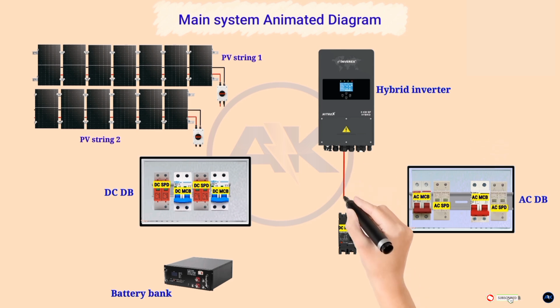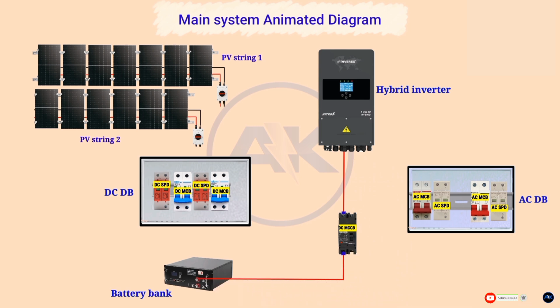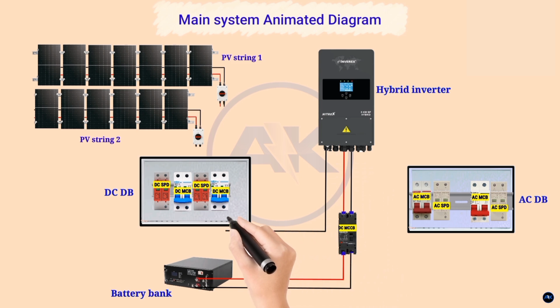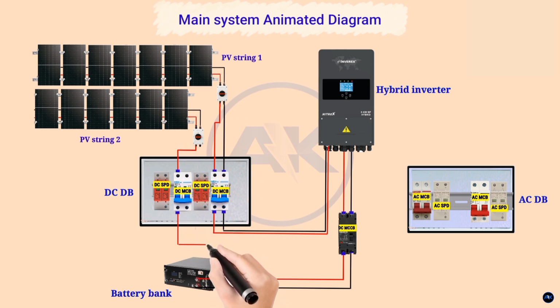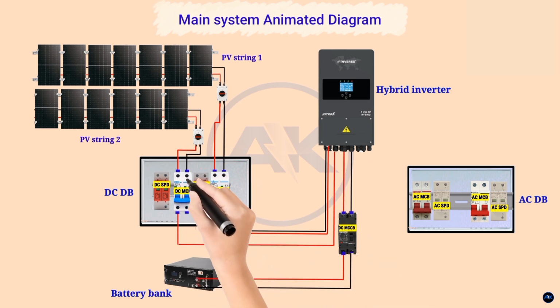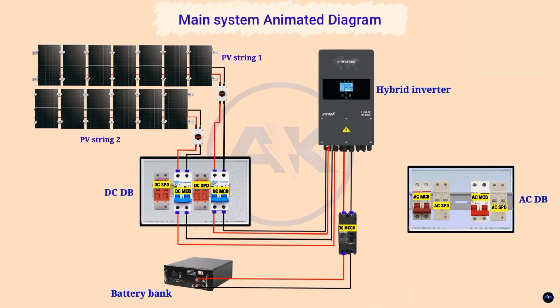Now we connect the DC MCCB to the terminals of the hybrid inverter, positive and negative, using the 2 AWG or 35 square millimeter battery cable. And let's proceed to connecting that to our battery bank. Then we can connect the DC MCB using the MC4 connectors on PV input number 1 of the hybrid inverter. And then we can proceed to the PV switch using again the same wires and another set of MC4 connectors. And don't forget to connect the DC SPD in parallel, using the 8 AWG or 10 square millimeter ground wire. We can connect the DC SPD output or ground to the bus bar, which is connected to our ground rod. Then we can connect the PV array output to the input of our PV switch.